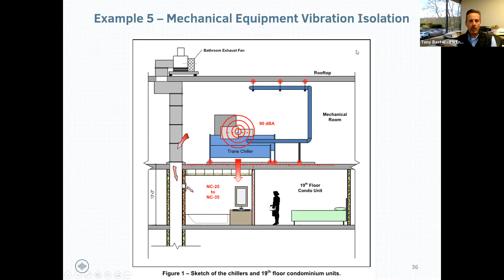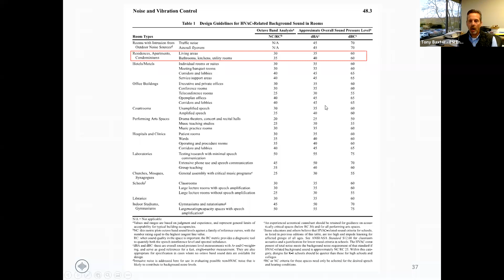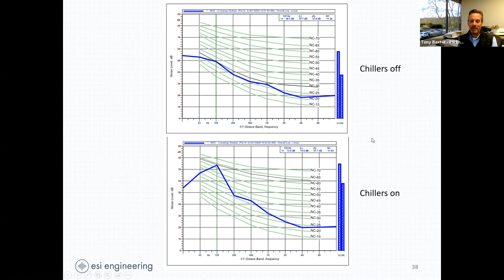And if we go into the ASHRAE guidelines, they say that for residences, apartments, condominiums, and living areas, NC 30, pretty good background noise level, right? 35 dBA, NC 30. So we went down there when the chillers were off. Here was the measurement. NC 30. There's the 30 curve, and there's the point of tangency right there. Turn the chillers on. NC 63. Right? You're paying all that money for the penthouse, and it's that loud. And the problem was definitely the two new chillers.